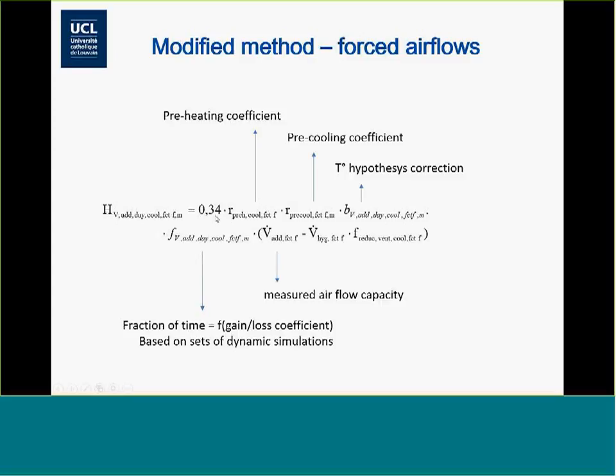For forced airflows, basically it's the same idea. You have a fraction of time, you have airflow. What's specific is that this airflow will be measured in situ. So the designer cannot make an assumption. He cannot just say, yeah, I will have so much air. He has to prove it. So it will be in situ measurements linked with measurements of the fan energy consumptions. I will go back to this just after. But basically, if the designers are not able to prove a real airflow, the default values will be set equal to the hygienic ventilation. So since here also you see we have a difference, the airflow for intensive ventilation, and we will deduce the airflow for hygienic ventilation in order to have a term that only counts for extra ventilation, additional ventilation above air quality level.